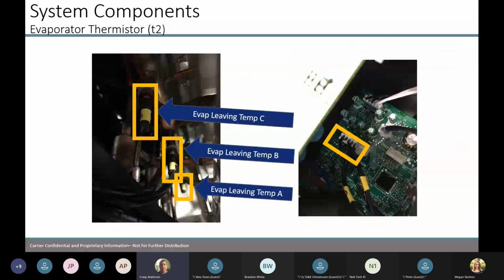So when we're dealing with multi-zone units, evaporating, leaving temperature, because we have multi-zones, each zone is going to have a sensor as well. So they can all modulate between each other and how they're going to operate. So be mindful of when we're opening up a unit, that the sensors are in the proper location, they're still attached. Very rarely that they come off, but we've seen it happen. They're on there pretty good. It takes a lot for them to come off.